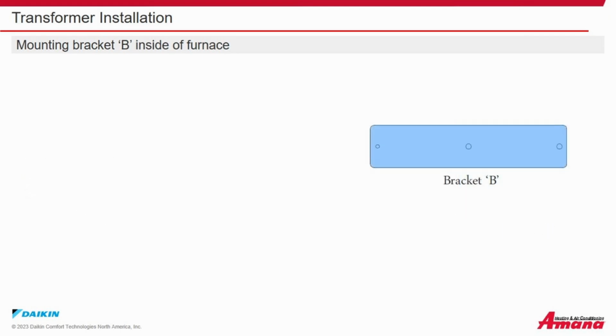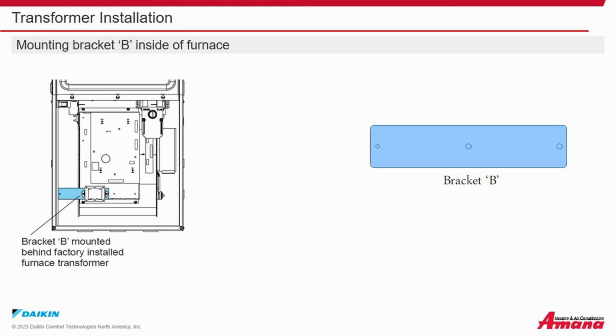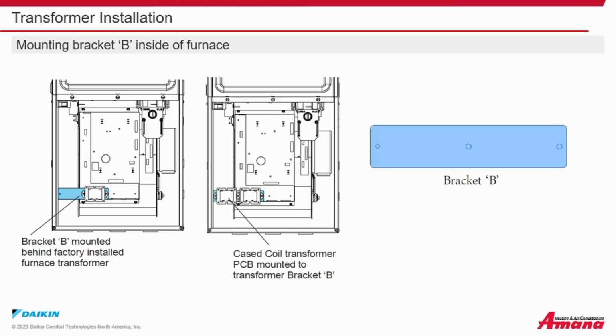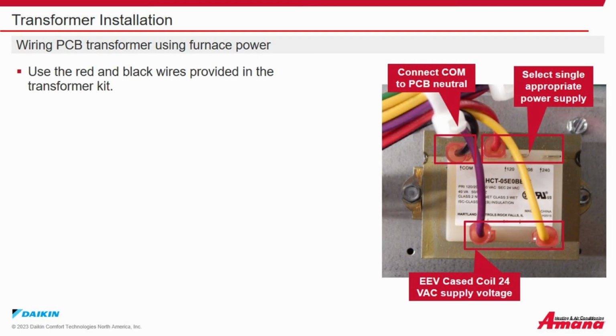Mounting bracket B inside of the furnace. This diagram shows bracket B mounted behind the factory-installed furnace transformer. And this diagram shows the cased coil printed circuit board transformer also mounted to transformer bracket B. Wiring the printed circuit board transformer using furnace power. Use the red and black wires provided in the transformer kit.